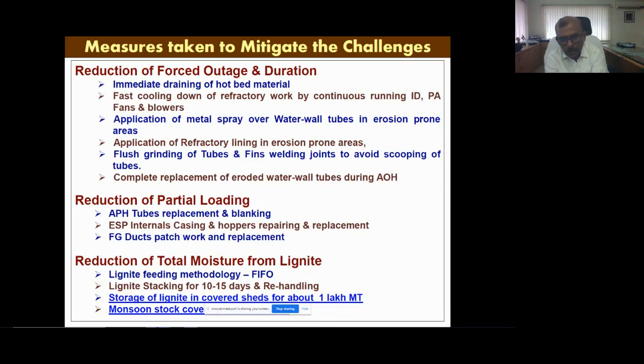For partial loading, as I told earlier, since the fuel has sulfur and chloride, there is heavy corrosion in the air preheater tubes, especially on the cold side, and that's why we need to change these tubes. Earlier we used to change them in 2 years, after a lot of modifications and process. Now we are replacing after 3 to 4 years based on the blanking. If it goes above 10 to 12%, we go for replacement. ESP, as already told, because of the sulfur and chlorine present in the lignite and moisture content, has a lot of corrosion, heavy corrosion.